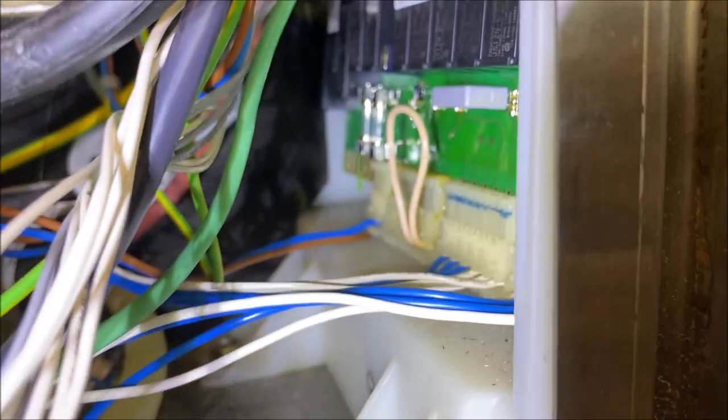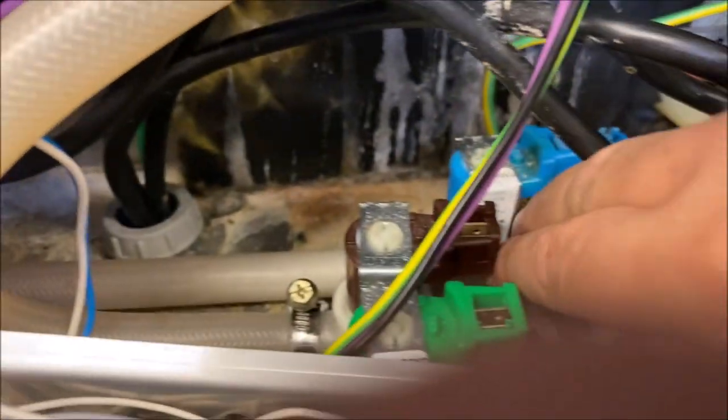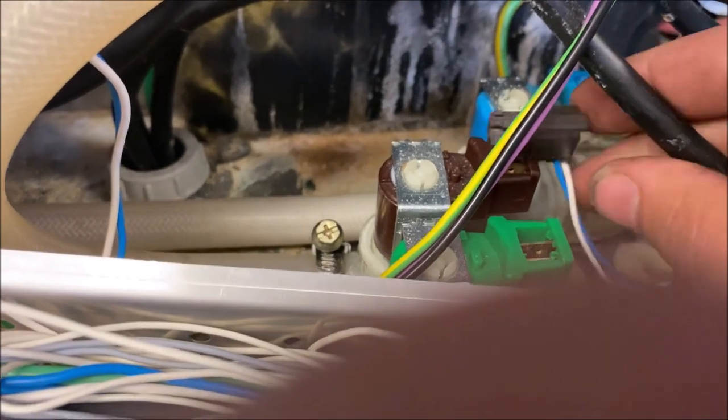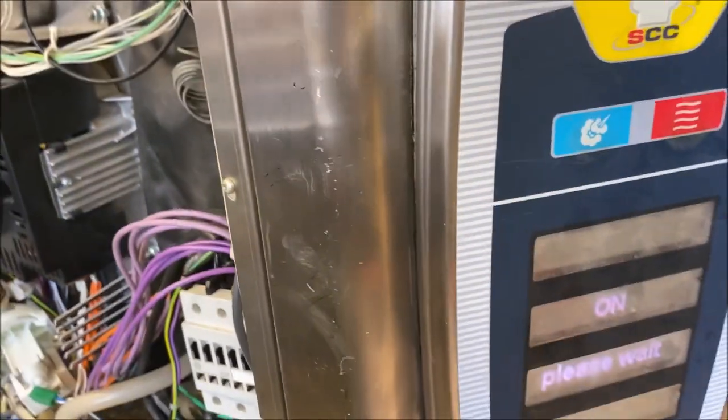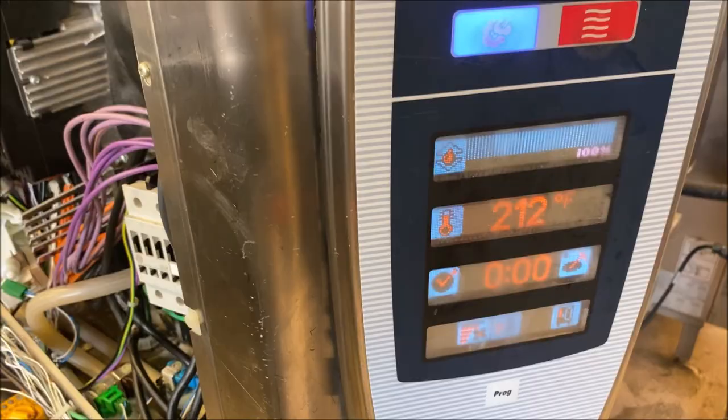The fuses did not blow, so that's good. That means the dead short is in one of these five components. Power down, of course. Let's hook back up our solenoids. If it blows, we know it's one of these three solenoids. It's usually not the solenoid. I'm leaning towards this clean jet pump.